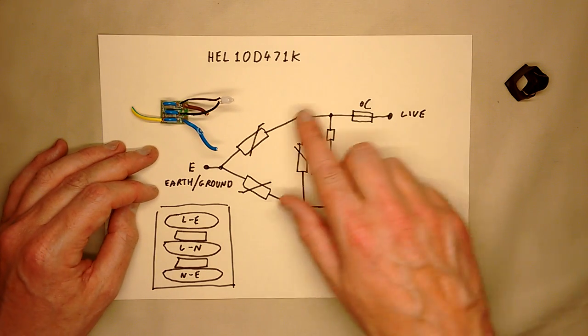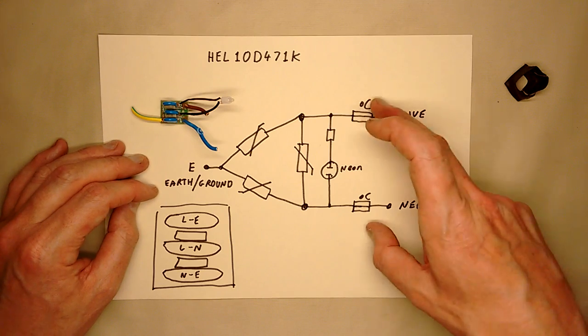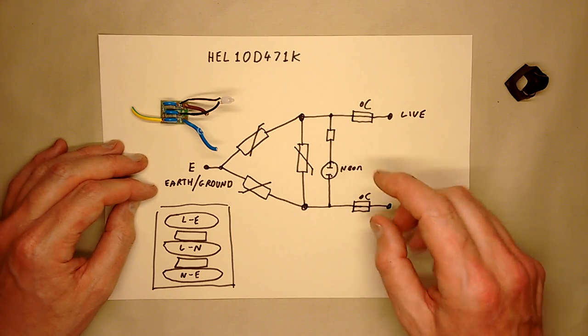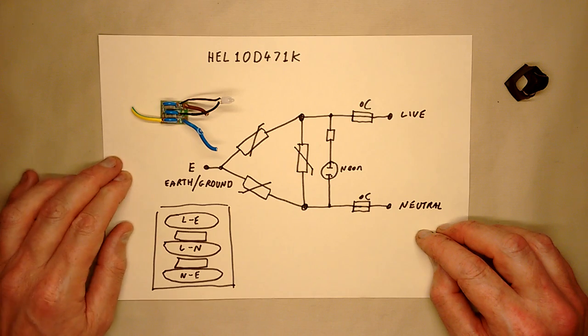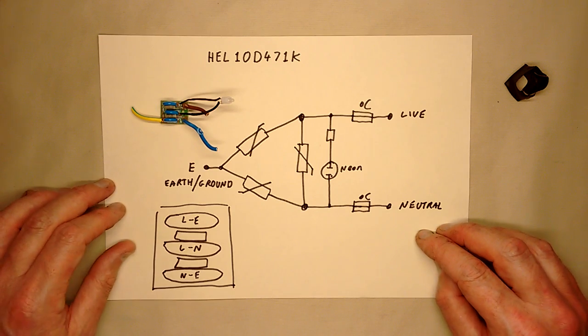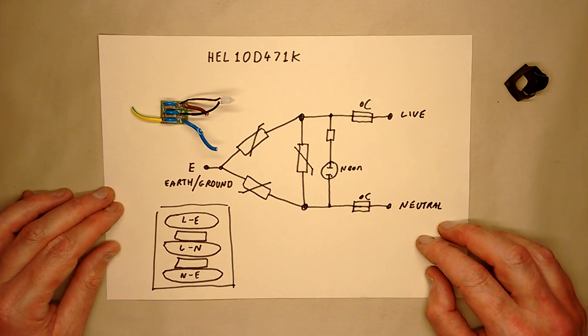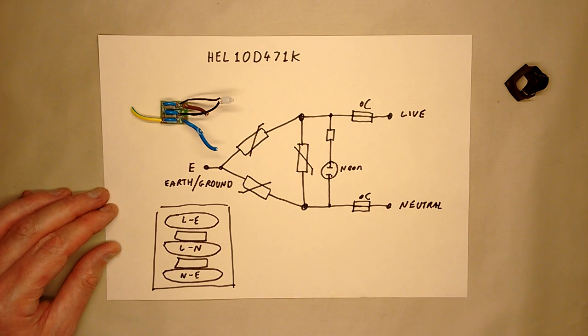But yeah, it's a perfectly functional little unit. It's got that thermal protection I like, and it's got the little neon that will at least give an indication if the protection has tripped due to a lot of transients or maybe a lightning strike or something. It looks pretty typical and a pretty good unit.